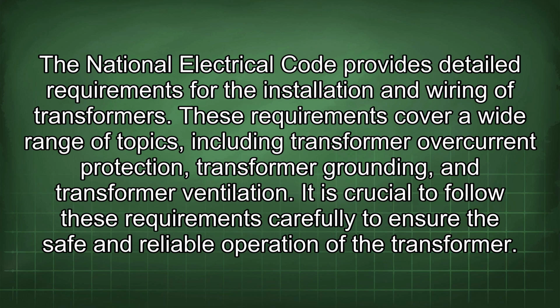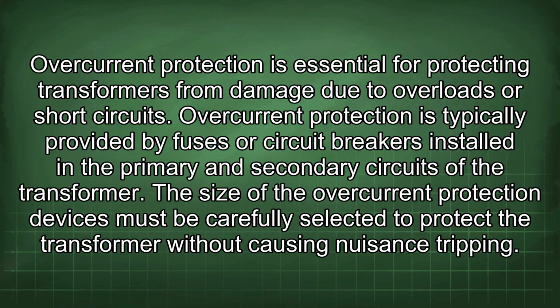The National Electrical Code provides detailed requirements for the installation and wiring of transformers. These requirements cover a wide range of topics, including transformer overcurrent protection, transformer grounding, and transformer ventilation. It is crucial to follow these requirements carefully to ensure the safe and reliable operation of the transformer. Overcurrent protection is essential for protecting transformers from damage due to overloads or short circuits. Overcurrent protection is typically provided by fuses or circuit breakers installed in the primary and secondary circuits of the transformer.